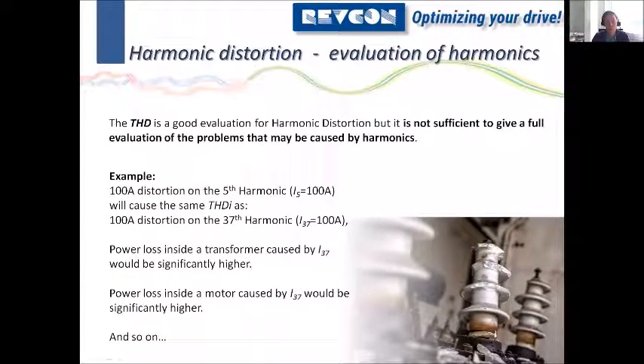That's for the fifth harmonic. For the seventh, it's a little bit worse. For the 11th, a little bit worse. 13, a little bit worse. But if you go up to the higher order harmonics, looking at the 37th, just as an example, this will be 1,850 hertz. Looking at this frequency, the transformer will not be able to transmit anything from this frequency to the next level. So we need to ask ourselves, where does this energy go? This energy is completely transmitted into heat inside the transformer.